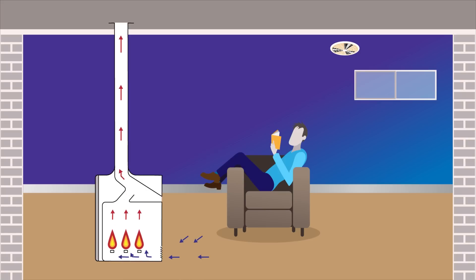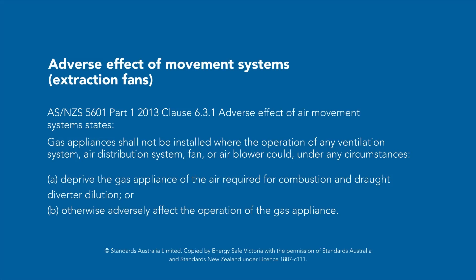If there is insufficient ventilation in the room or building, the installation is non-compliant and additional ventilation is required. AS NZS 5601 Part 1 2013 Clause 6.3.1 Adverse effect of air movement systems states gas appliances shall not be installed where the operation of any ventilation system, air distribution system, fan, or air blower could under any circumstances deprive the gas appliance of the air required for combustion and draft diverter dilution or otherwise adversely affect the operation of the gas appliance.